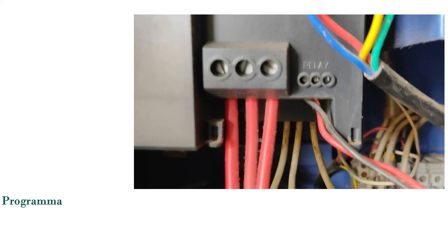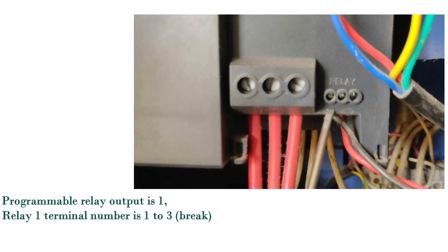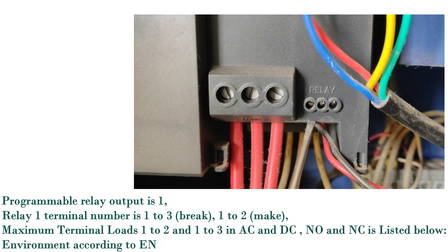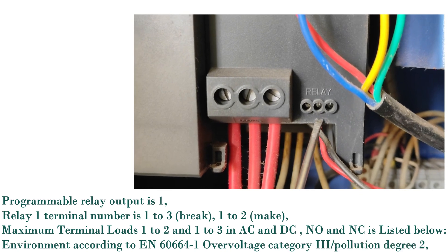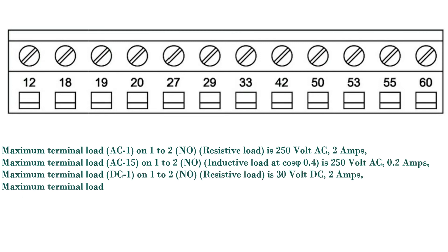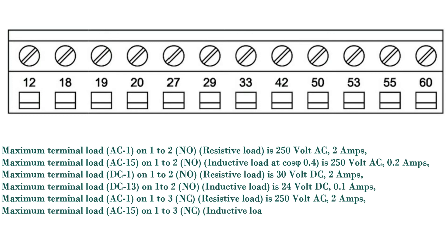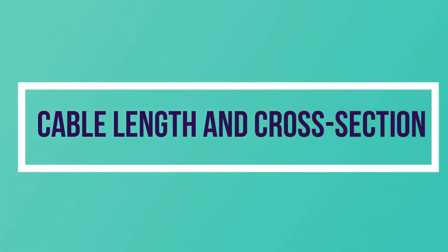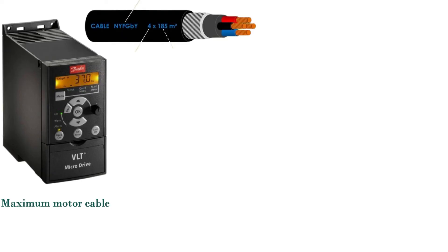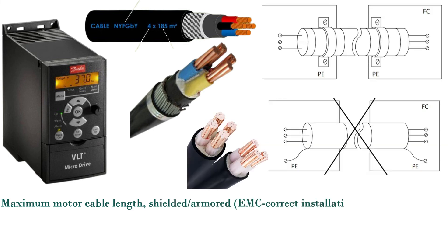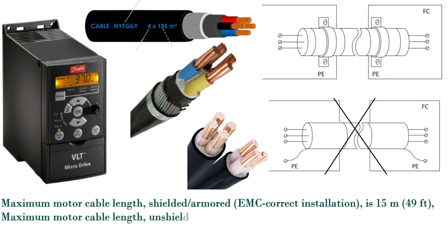Relay output: programmable relay output is 1. Relay 1 terminal numbers are 1 to 3 (break) and 1 to 2 (make). Maximum terminal loads 1-2 and 1-3 in AC and DC — NO and NC — are listed per environment according to IEC 60664-1 overvoltage category 3/pollution degree 2. Maximum motor cable length shielded/armored (EMC correct installation) is 15 meters (49 feet); maximum motor cable length unshielded/unarmored is 50 meters (164 feet).